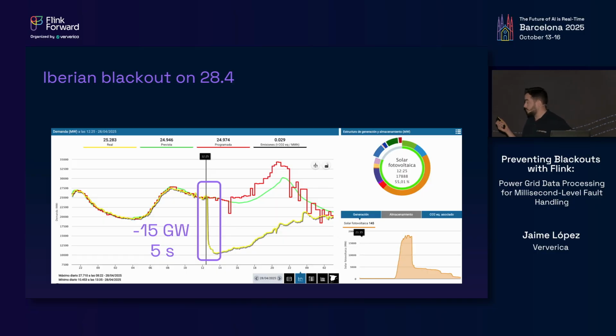The day that the blackout happened, Spain lost 15 gigawatts of generation, which is about 70% of the capacity of that moment, in 5 seconds. This is what caused the blackout. If you catch this before these 5 seconds elapse, you would have avoided the blackout. And the big takeaway is that speed matters, speed kills or keeps you alive, and you can actually solve this purely by being fast.